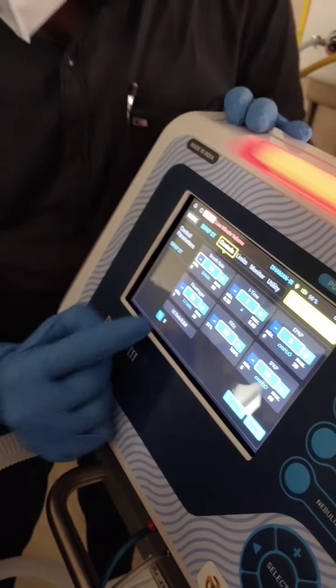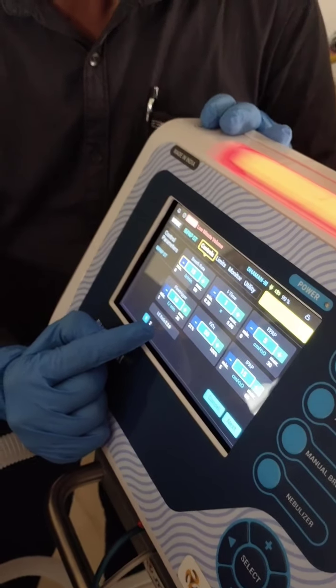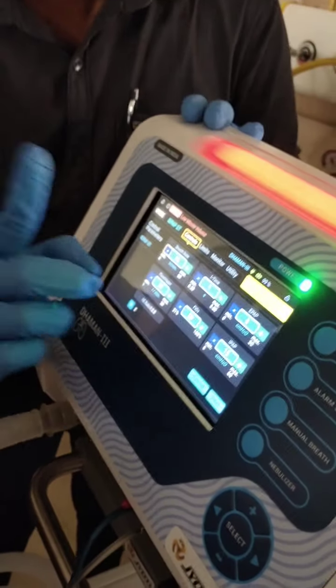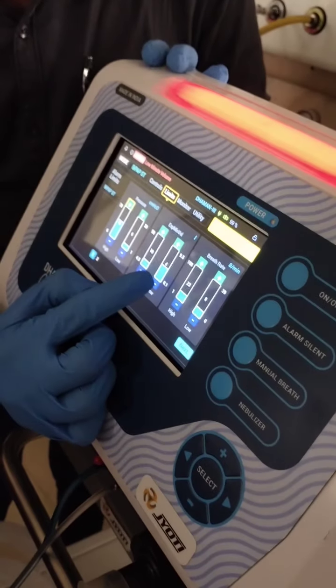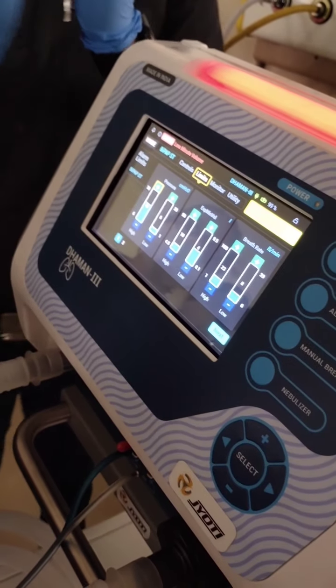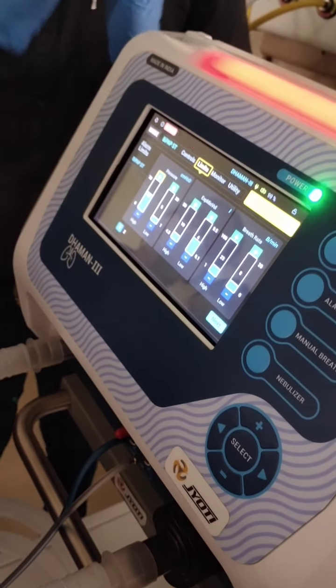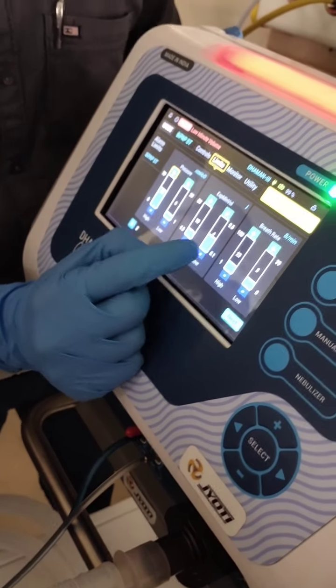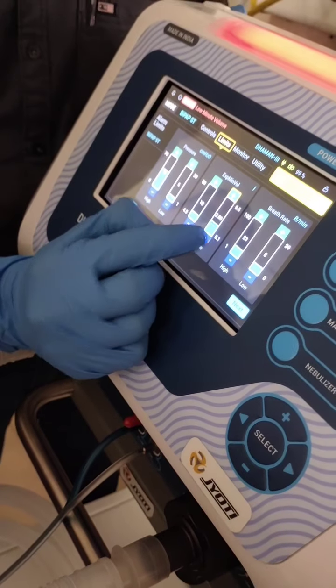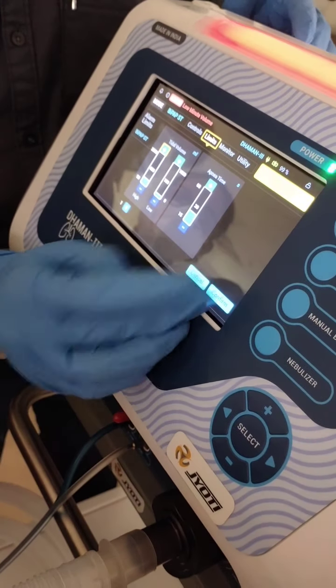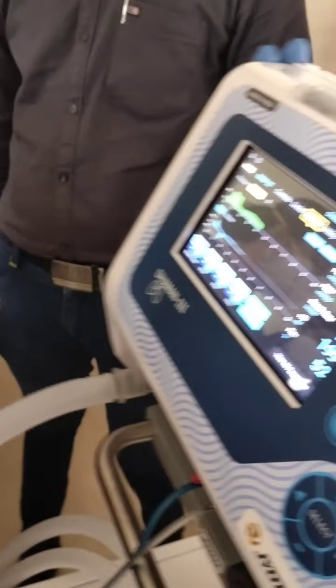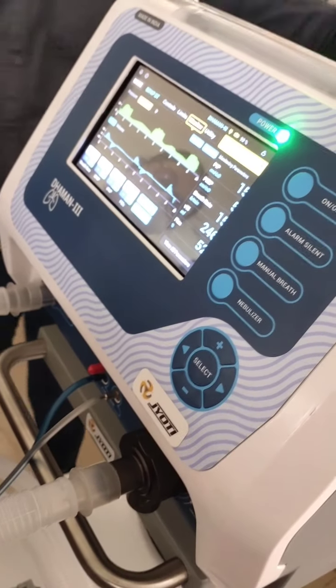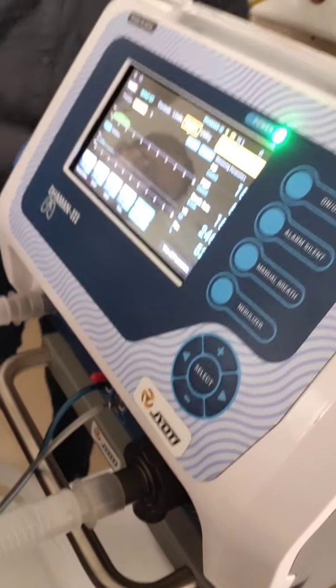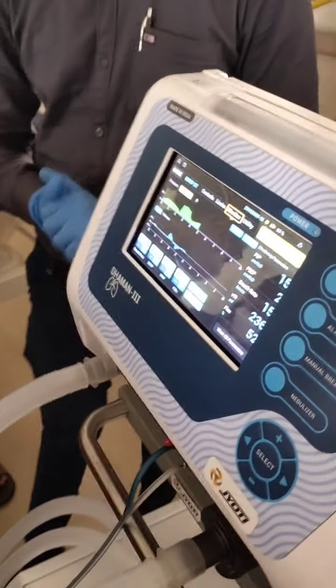Why I am telling you to reduce is that the IE ratio is 1:3. But here the inspiration time starts at 1 second, and in the limits it should be 4. So you tell now, you reduce it now to 1:4. That's why the error comes here. So you have to reduce it to 2 or 1.5. If you reduce the minimum value, the error won't come. Now you are understanding. Now the error will be clear. So like that, these are the basic methods.